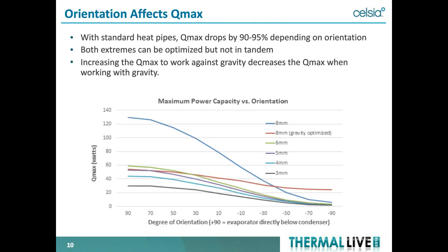How does orientation affect performance? A lot depends on the wick structure and whether it was designed to work against gravity. A chart shows performance of different diameter heat pipes versus gravity angle — from positive 90 degrees (heat source at bottom, cooling at top) to minus 90 degrees (reversed). Once you get to around minus 30 degrees, performance really drops off. However, with gravity optimization on an 8-millimeter heat pipe, you can see significantly better performance against gravity.